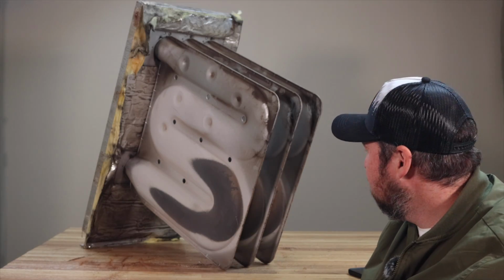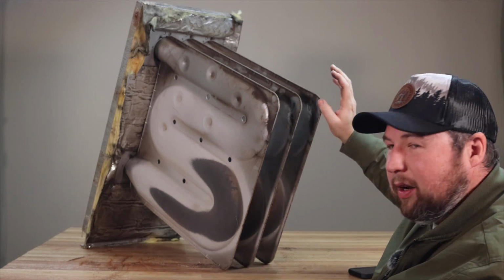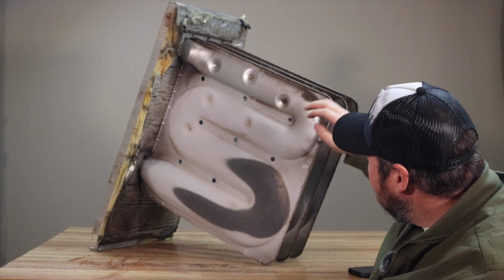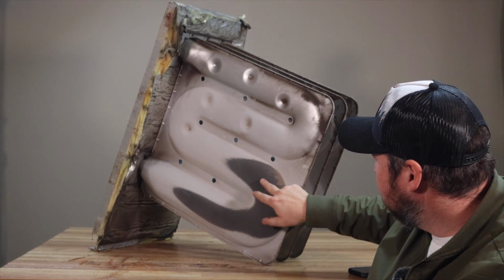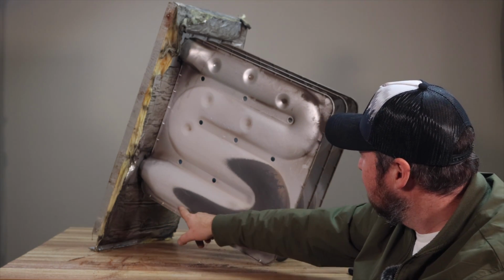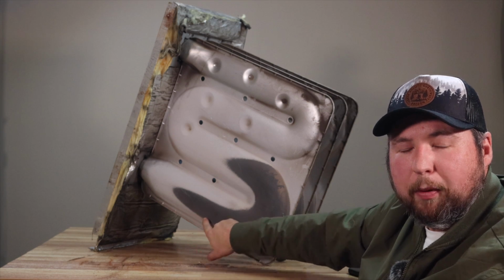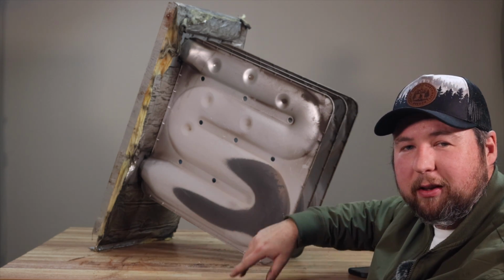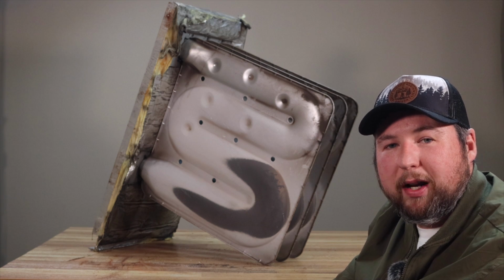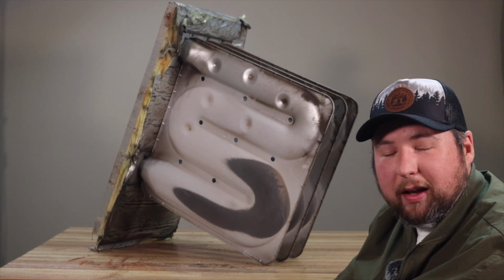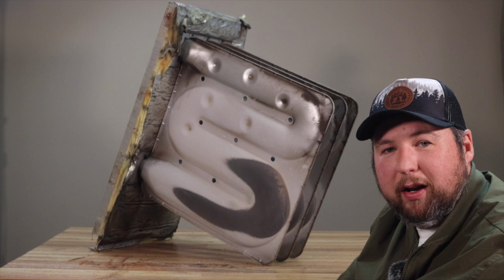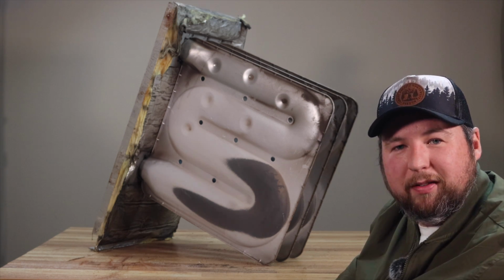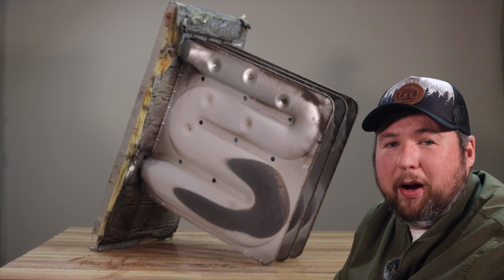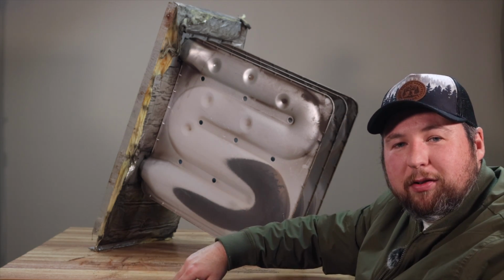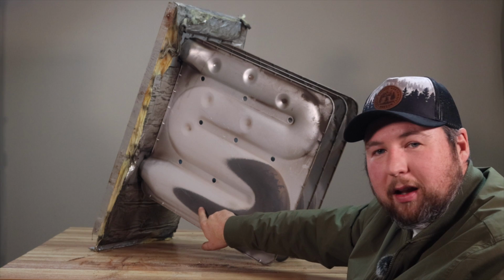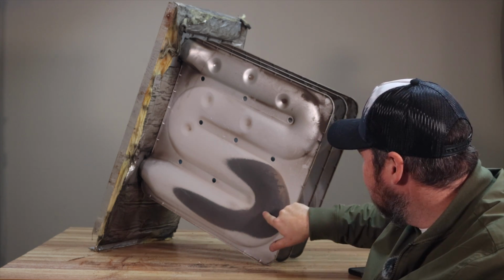Here's a serpentine heat exchanger. This one has some cracks. Now, you can see here, we have our temperature stress points, right? Right in the combustion area, you can see. Now, this was probably due to overfiring. This particular unit, the blower motor had failed, and it kept running, right? So basically, the high limit would trip, it'd reset and run and run and run. High limit would trip, reset, run and run and run. This happened for quite a long time. And on top of that, the gas pressure wasn't set properly. So we had a lot of overheating. So you could see how dark these parts are.